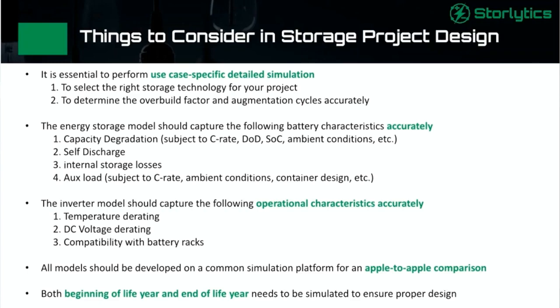You have to make sure your energy storage model that you are using is able to capture the following factors very accurately, like capacity degradation. There are several things that can impact your degradation. Now those vary from technology to technology, but for lithium, your C rate, depth of discharge, temperature, those play a very vital role. There are some other technologies where these factors might not be as impactful, but you need to have a very accurate model of degradation that can reflect all these different factors and their interplay. Self-discharge needs to be modeled correctly, and you need to have your internal storage losses, like your RTE losses.